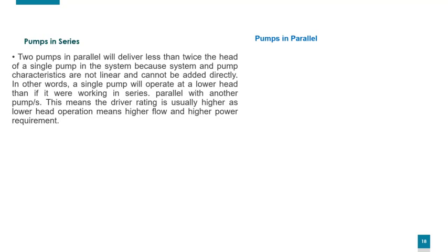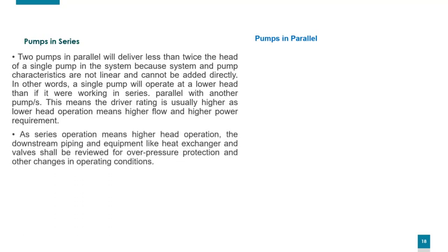So, pumps in series. Two pumps in series will deliver less than twice the head of a single pump in the system because system and pump characteristics are not linear and cannot be added directly. In other words, a single pump will operate at a lower head than if it were working in series with another pump. This means the driver rating is usually higher, as lower head operation means higher flow and higher power requirement. As series operation means higher head operation, downstream piping and equipment like heat exchanger and valve shall be reviewed for overpressure protection and other changes in operation conditions. Consult the pump vendor and get the scheme approved by pump vendor.